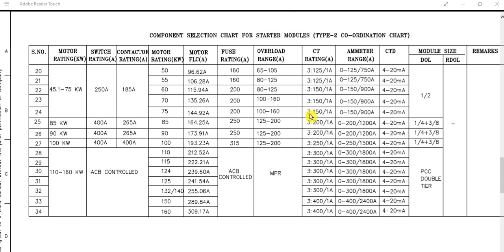And this is the CT rating. This is 3 numbers of CTs, and the CT ratio, current transformer ratio, is 150 by 1 ampere. That means the CT primary current is 150 ampere. Accordingly the secondary current will be 1 ampere. So CT secondary is 1 ampere, 3 number CTs here. And this is the ammeter range, 0 to 150 by 900 ampere. This is the ammeter range.